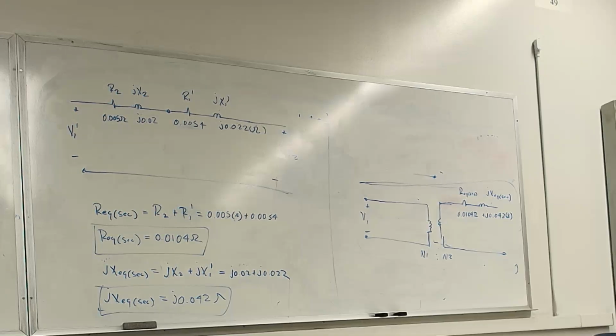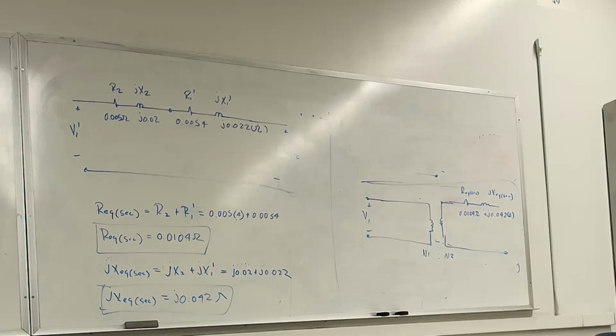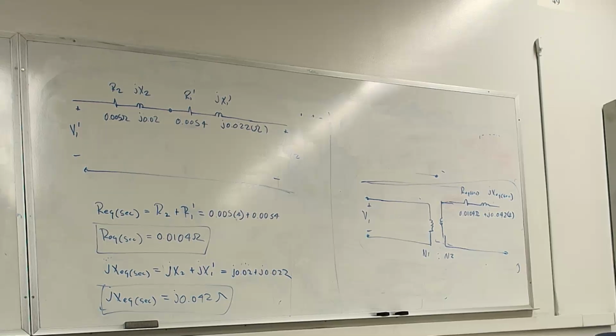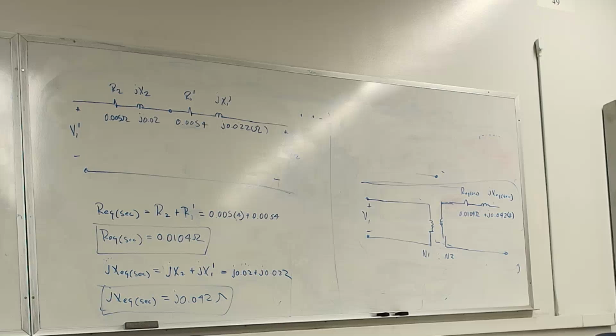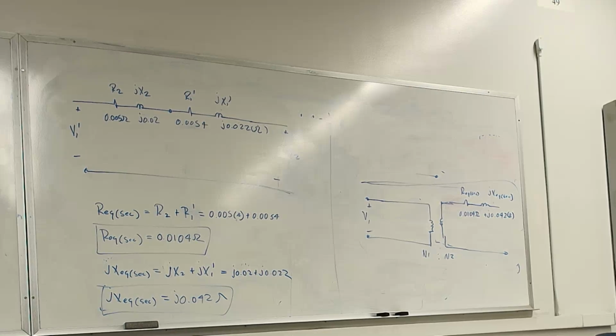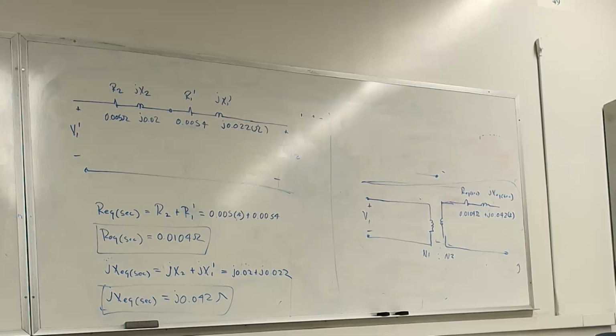I see books that just throw numbers, and I get it. You're teaching. It's math, right? But that's not the case. That is what I call a realistic example. There's no such thing. The resistance in comparison to the reactance is so much smaller. You'll hear them say the transformer X over R ratio is really high. Yes, because if you divide X by R, the number should be high.